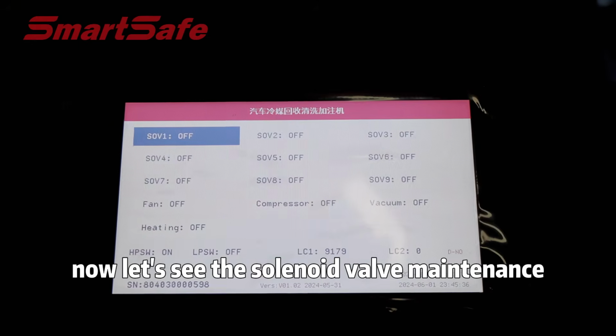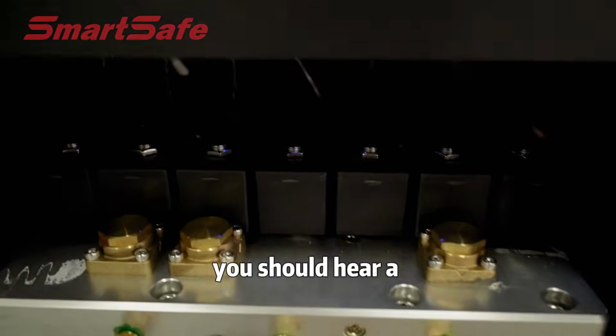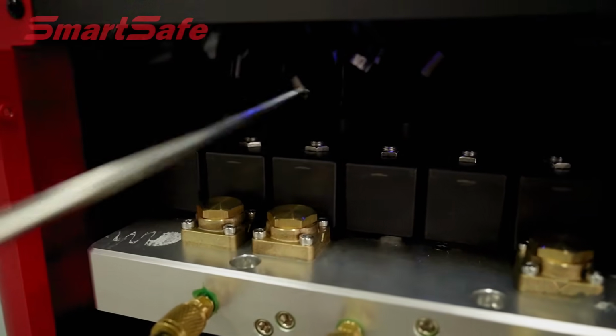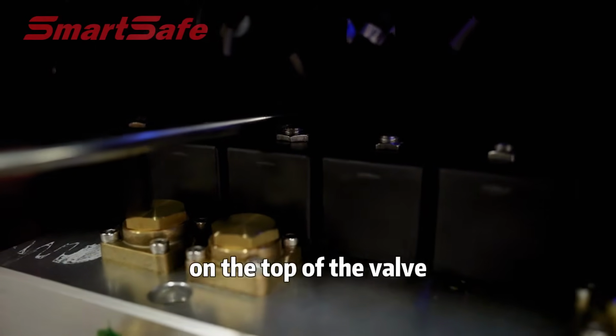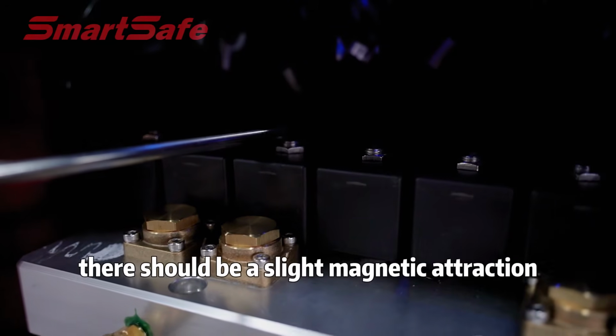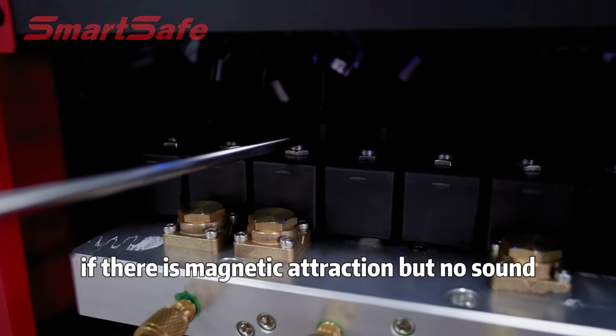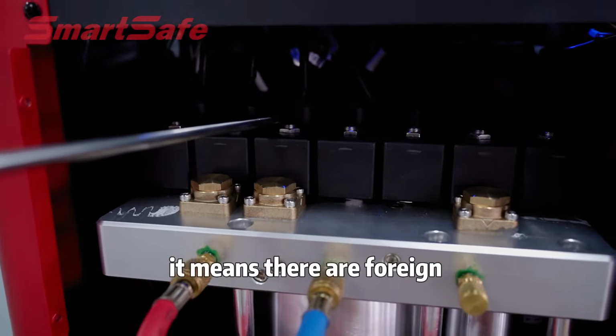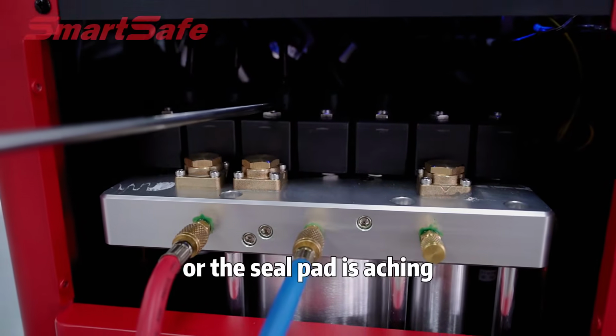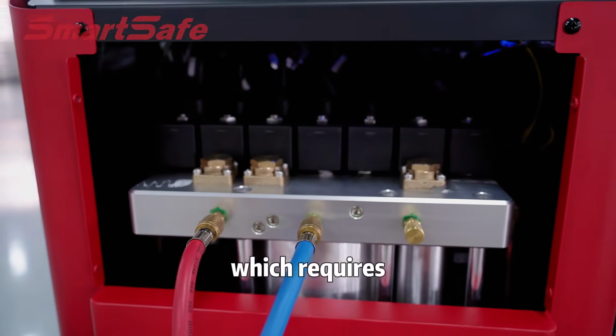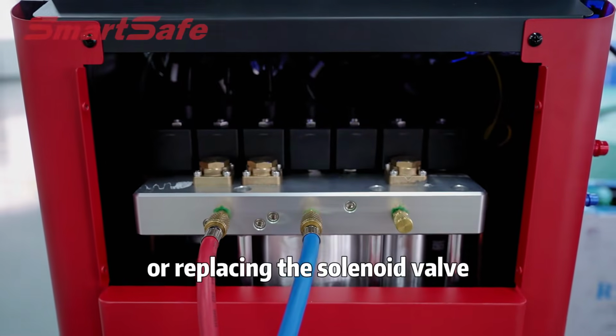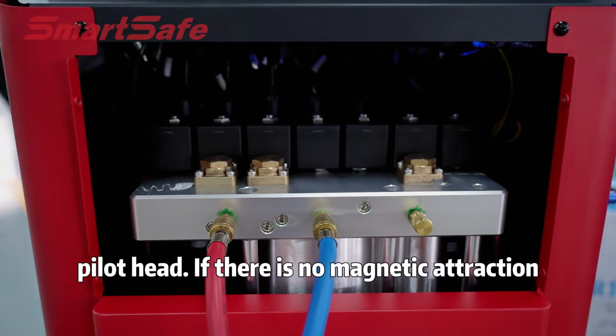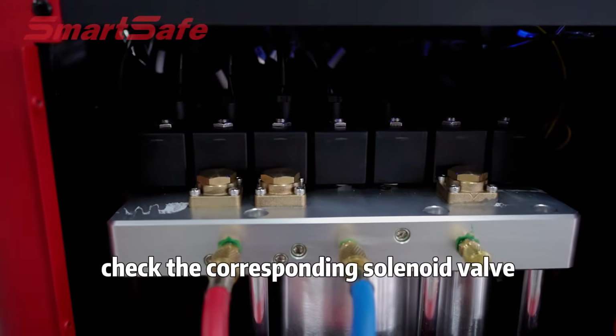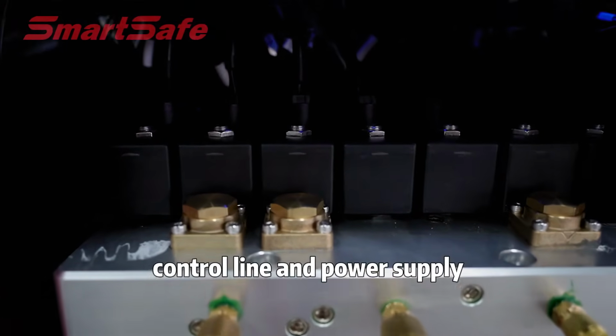Now let's see the solenoid valves maintenance. You should hear a click sound when it operates. Place a metal screwdriver on the top of the valve. There should be a slight magnetic attraction. If there is magnetic attraction but no sound, it means there are foreign objects inside the valves or the seal pad is aging, which requires cleaning or replacing the solenoid valve pilot head. If there is no magnetic attraction, check the corresponding solenoid valve control line and power supply.